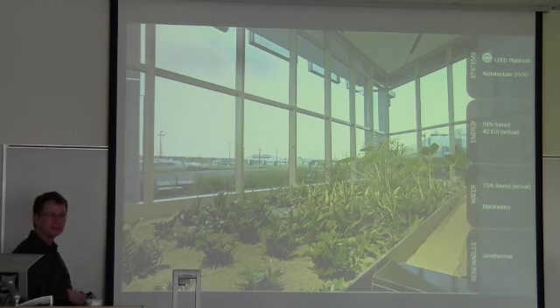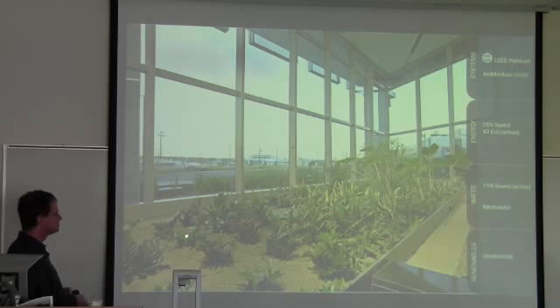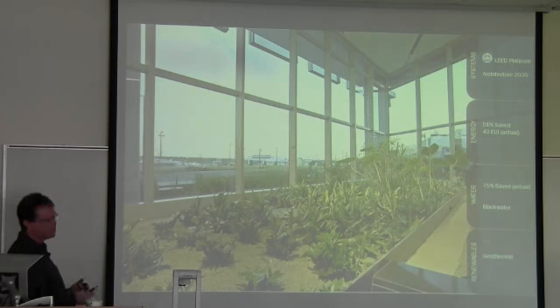wetlands bed system. Worrell Water Technologies is a company that's currently licensed for living machine application. Basically, in the world of on-site waste treatment, there's membrane bioreactor, which is a very mechanical process. That's OHSU health and healing building down at the foot of the tram, or there's this, which is a more passive approach with just basically batching water from tank to tank and letting the enzymes and the biological components happen within a tank basis here to provide the clarification and the removal of the nutrients in the water. So those are the two main systems that are in play for buildings right now.